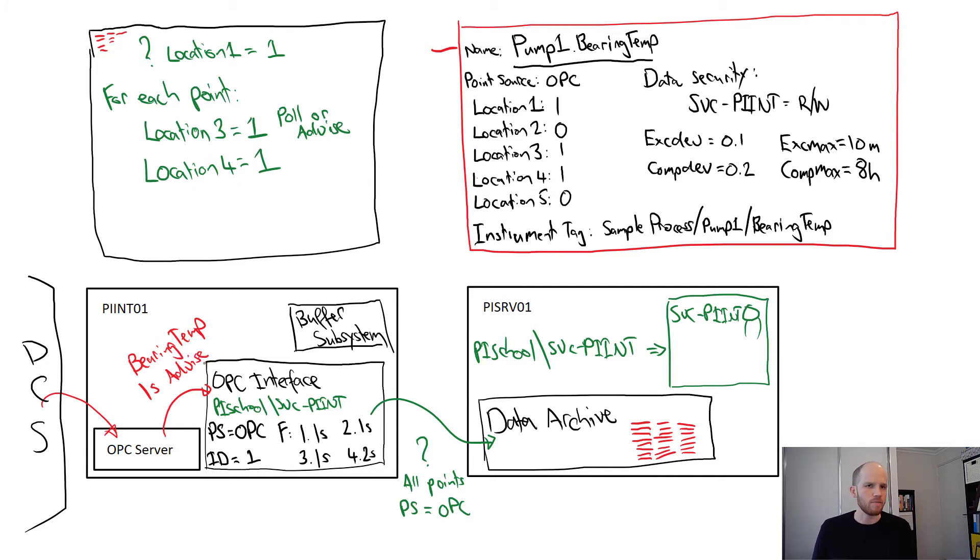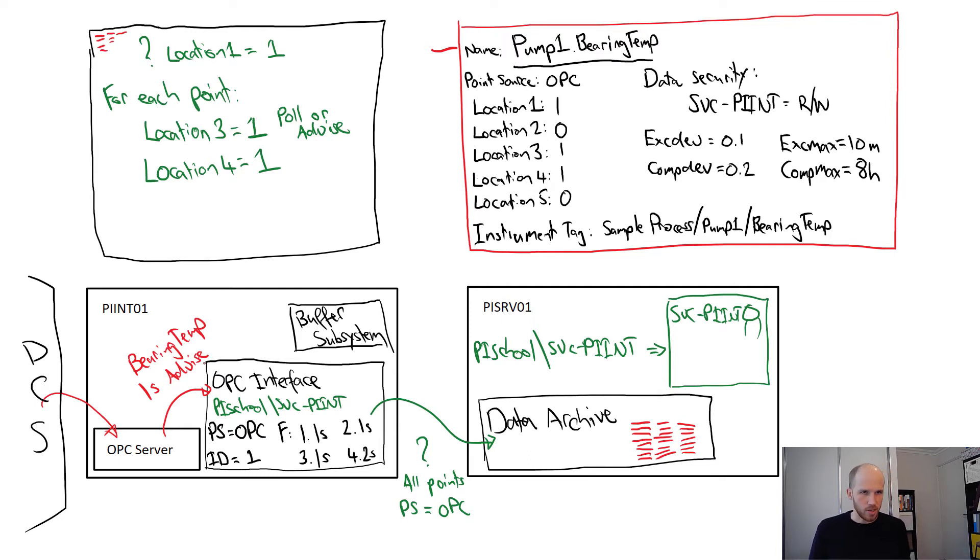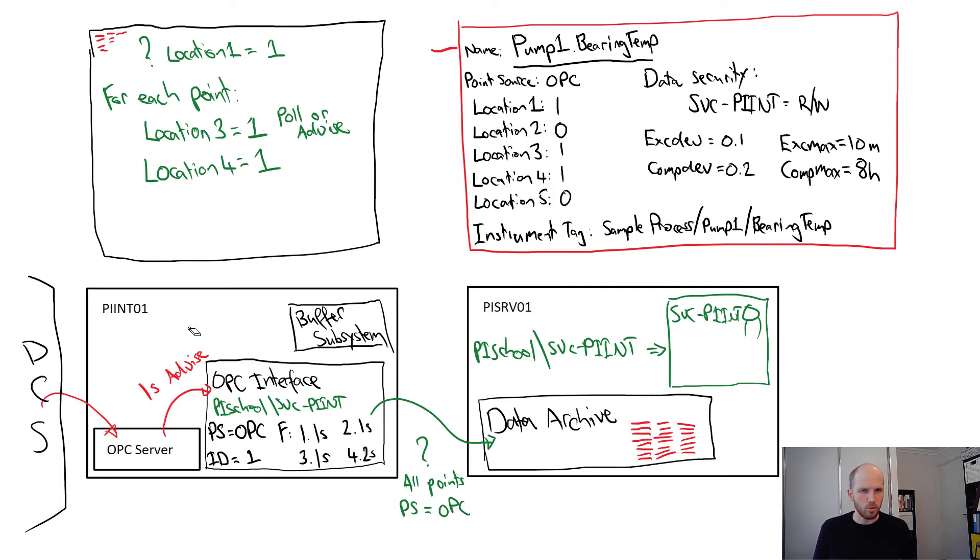Because it's an advise tag, this effectively means that the interface connects and says, hi OPC server, send me through any update you've got for the bearing temp tag, but no more often than every 1 second.